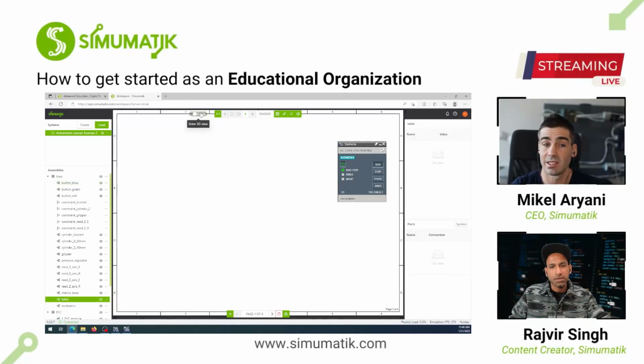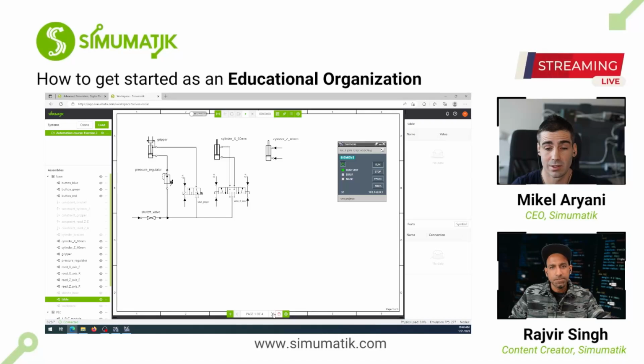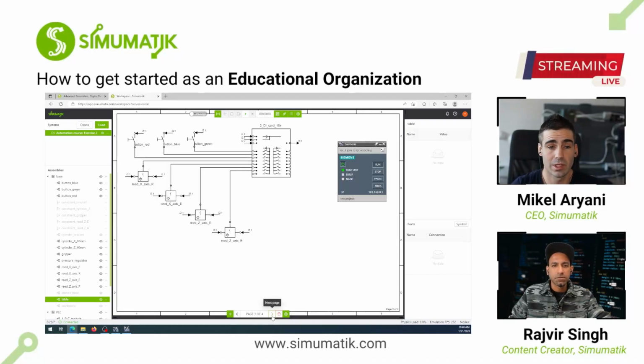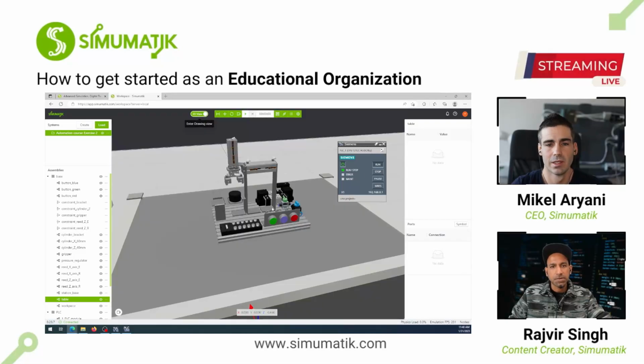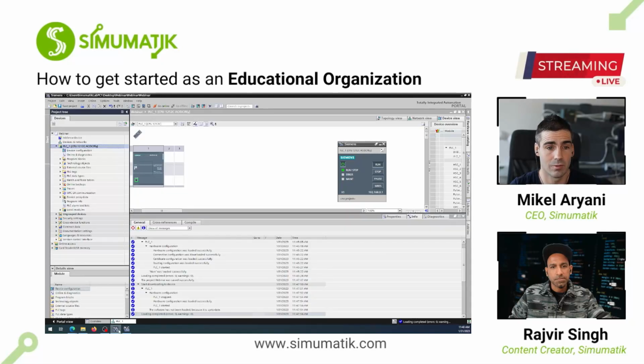We can see that as well if we check the drawings, because this system has the drawings. So we could go here, and here we see button green to input 00, input 01, and the same for the outputs. We have 00 and 01: 00 to retract the x-axis, and 01 to extend the x-axis. So let's say we want to work with those variables.